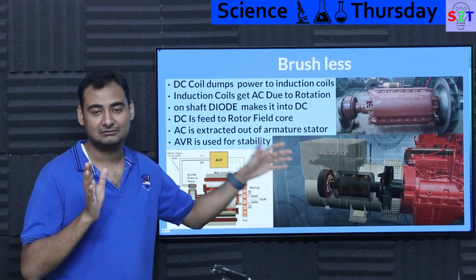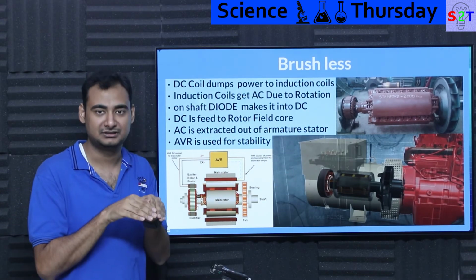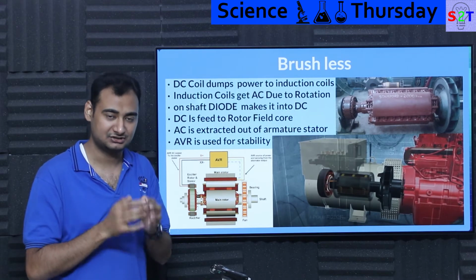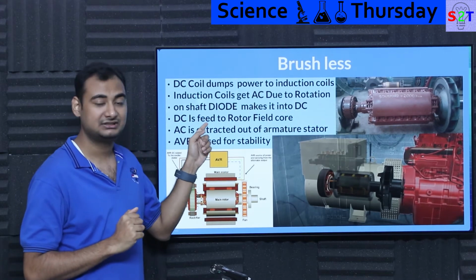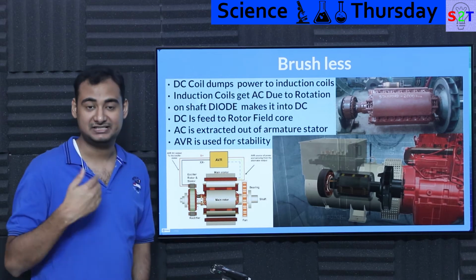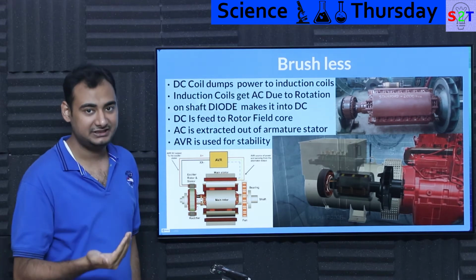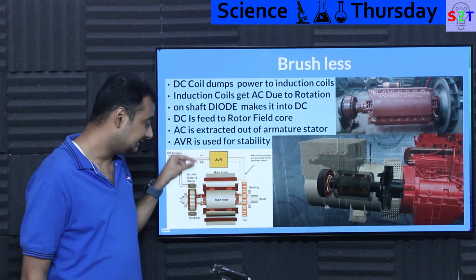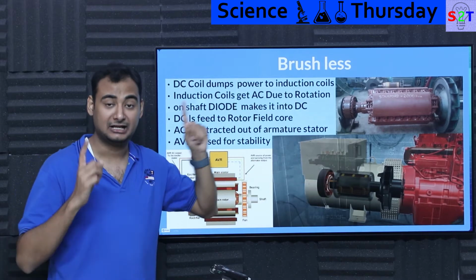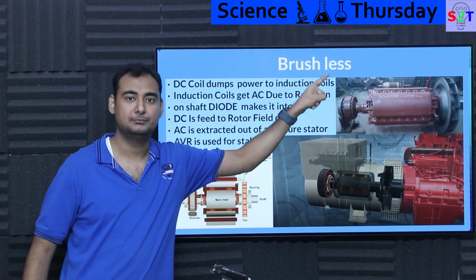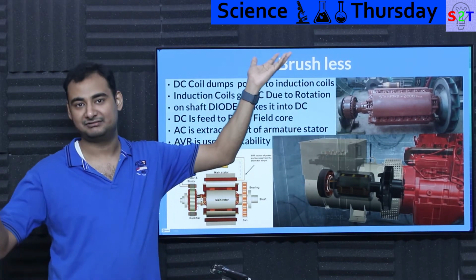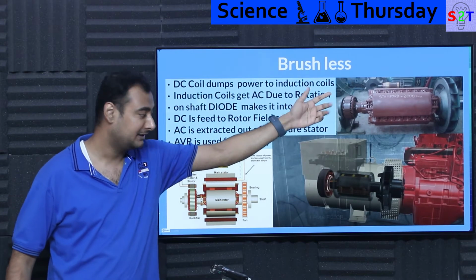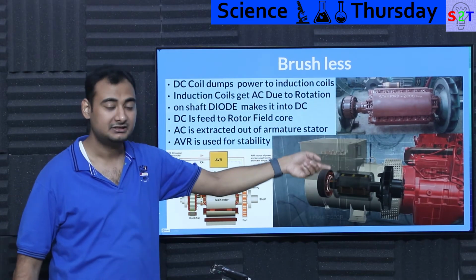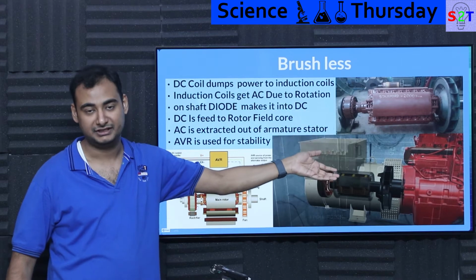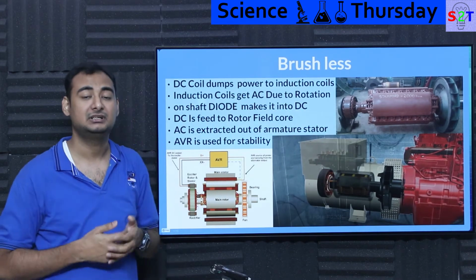Now you have to solve the issue of brushes. You've dumped energy into the system without requiring a brush, that's awesome. After that, you send it through what we call a diode rectifier stage, to turn the AC into DC. Once you do that, that DC is fed into the main rotor, and the main rotor acts as an electromagnet. At that point you have a generator: a magnet rotating inside a stator. The stator has armature windings around it, and you tap off that winding for electricity.